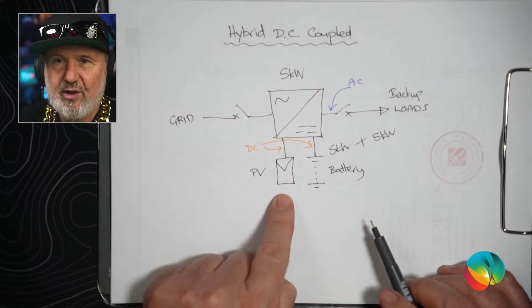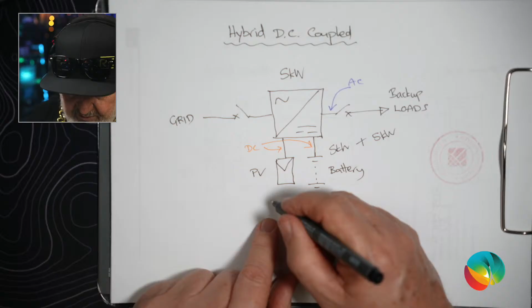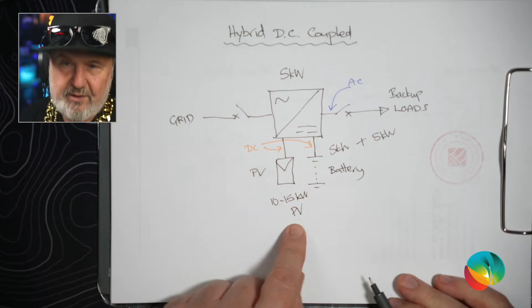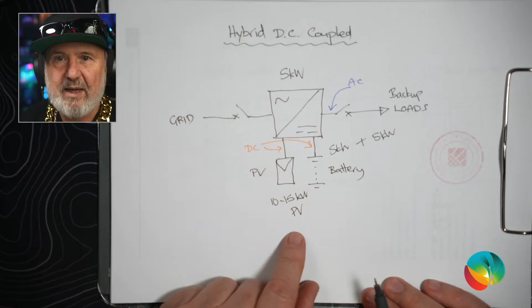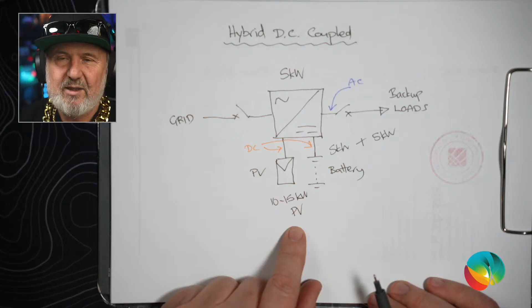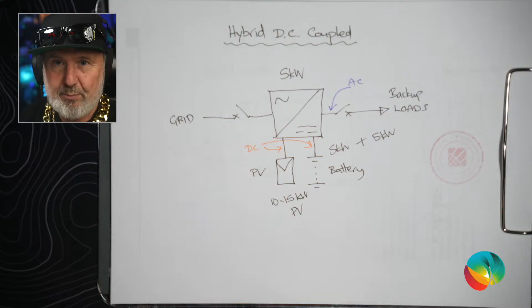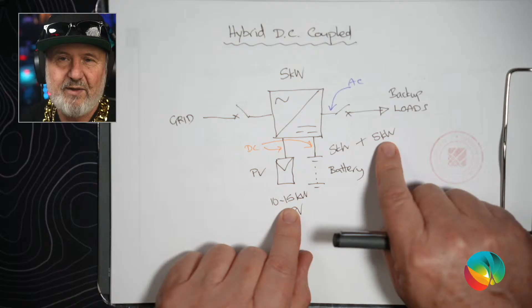So what does that mean? It means you want to have a lot more PV. If you've got this capability in a hybrid inverter, I'd say you probably want 10 to 15 kilowatts of PV. Of course, you've got to consider the manufacturer's limits on this. So manufacturers will often give you a DC power limit, sometimes called an oversizing limit, typically 150%, sometimes 200%, sometimes 250%. It's all about the product and how it's designed. Why would you want 15 kilowatts though, when the maximum you can ever utilize is 5 kilowatts of DC charging and 5 kilowatts of AC power?